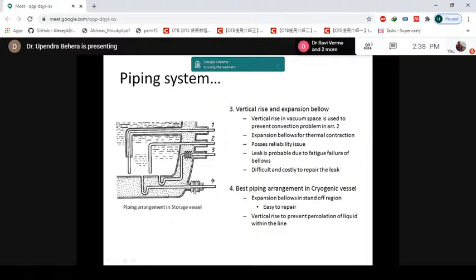So the best piping arrangement in the cryogenic vessel is the use of expansion bellows in the stand-off region. Stand-up area means here, because this outer shell is generally carbon steel, and inside is generally SS304 or so, and it's thin-walled. Here you can go for carbon steel and the thickness can be more. But when you are using SS pipe to the inner container, when it goes through this carbon steel container, it cools down and it may damage this area. So if this part is stainless steel again, then this bellows can be welded and put there. So they have put the bellows in the stand-off region, and as I told, because it's outside the outer container, it can be easily repaired.